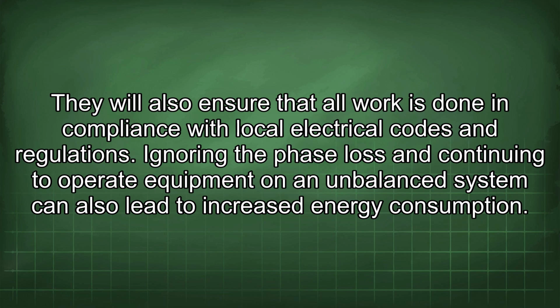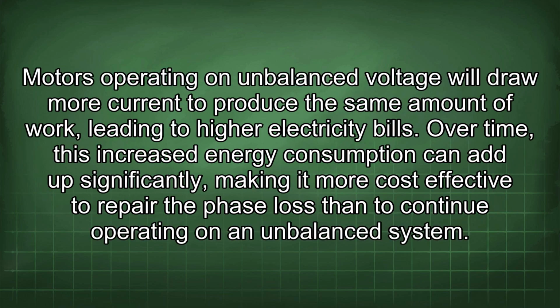Ignoring the phase loss and continuing to operate equipment on an unbalanced system can also lead to increased energy consumption. Motors operating on unbalanced voltage will draw more current to produce the same amount of work, leading to higher electricity bills. Over time, this increased energy consumption can add up significantly, making it more cost-effective to repair the phase loss than to continue operating on an unbalanced system.